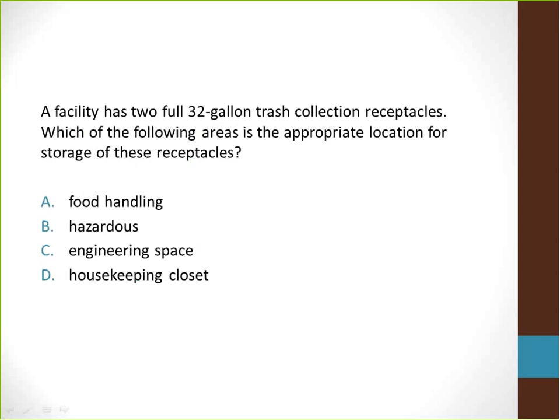A facility has two full 32-gallon trash collection receptacles. Which of the following areas is the appropriate location for storage of these receptacles? A, food handling; B, hazardous; C, engineering space; D, housekeeping closet. Answer B is the best answer here because according to NFPA 101, a facility may exceed the 32-gallon limit in a hazardous area.